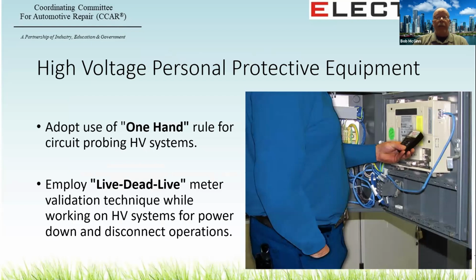So I have to ask a rhetorical question here: who's teaching the one-hand rule or live dead live? Veterans of high voltage work will traditionally use the one-hand rule when working on a high voltage circuit. This means that only one hand at a time can be used to work on a high voltage circuit. The purpose of the rule is to reduce the risk of electrical shock that has the potential to cause cardiac arrest from passing through the student, through the torso. This discipline will add an additional layer of safety to the protection already afforded you by rubber gloves and other personal protective equipment. Now, to adhere to the one-hand rule, when taking a direct voltage reading, it is essential that you have at least one electrical lead that is equipped with a properly rated insulated alligator clip.